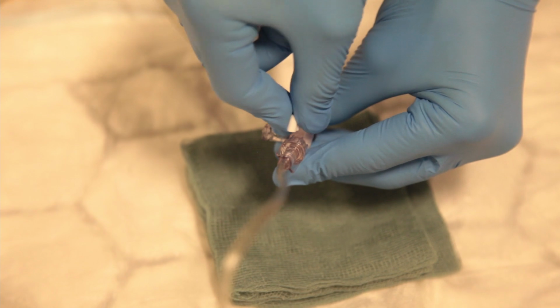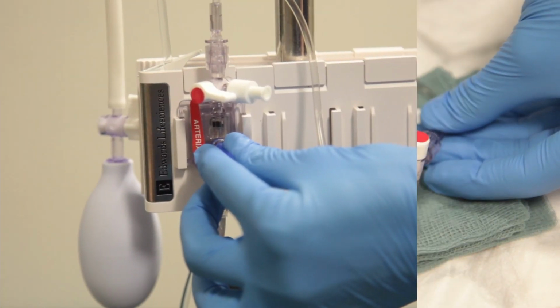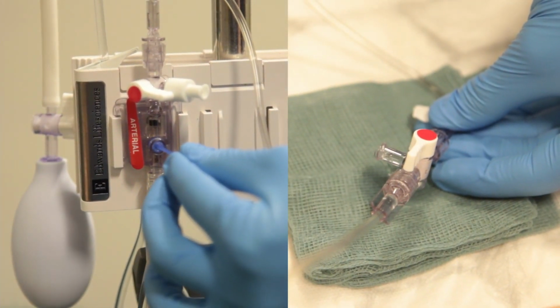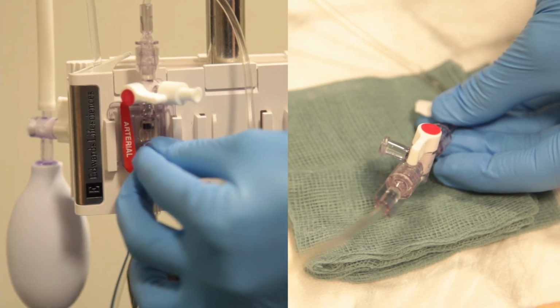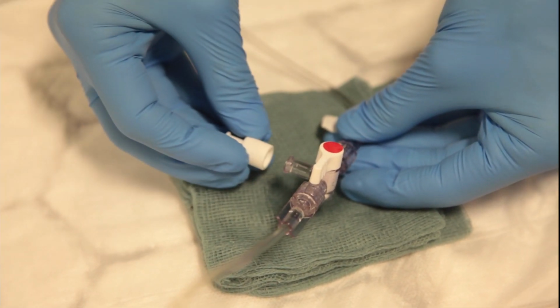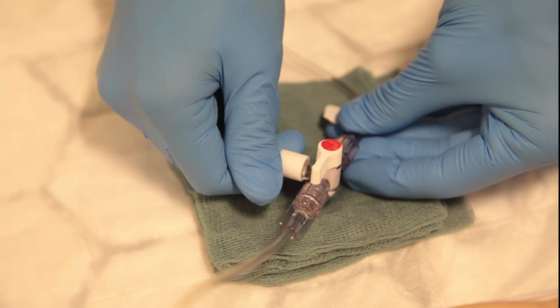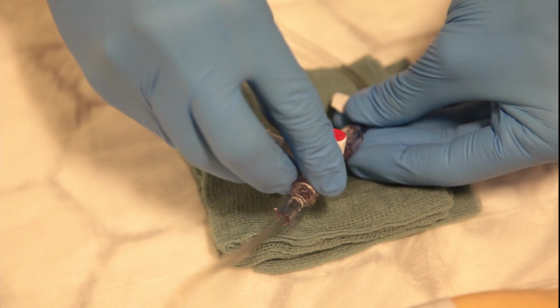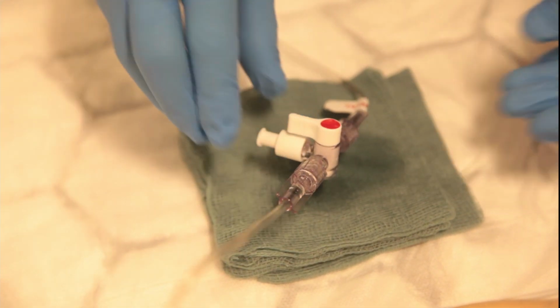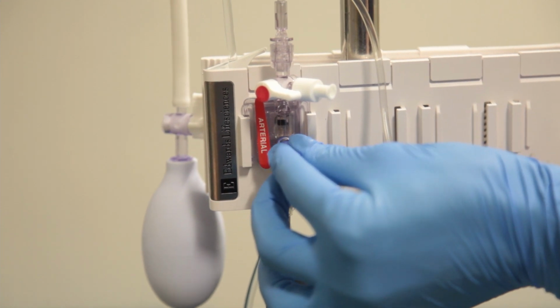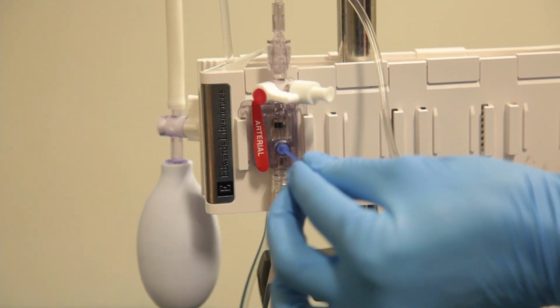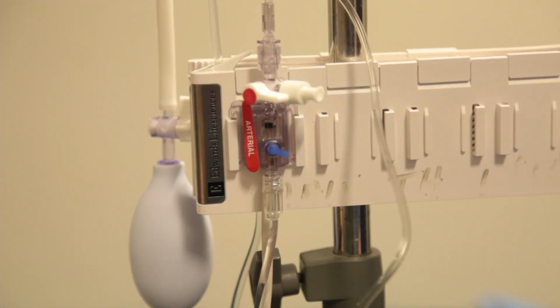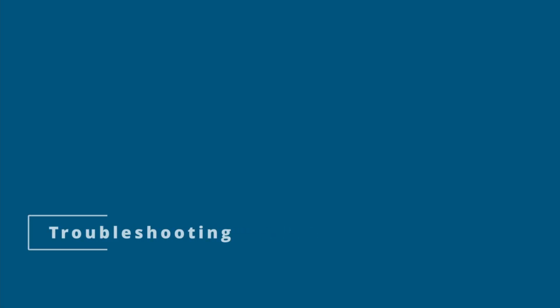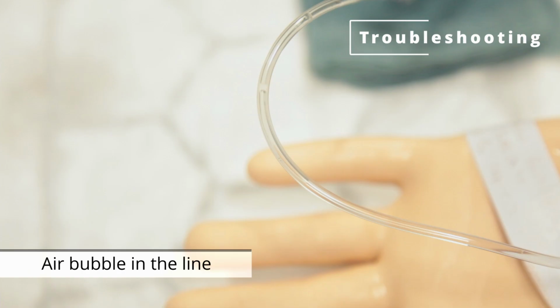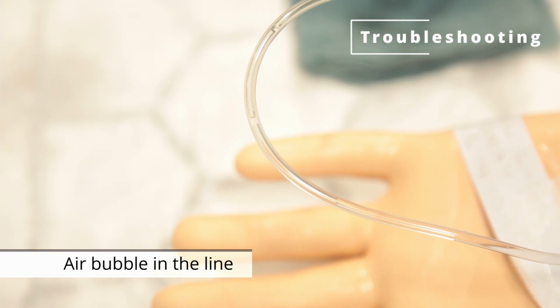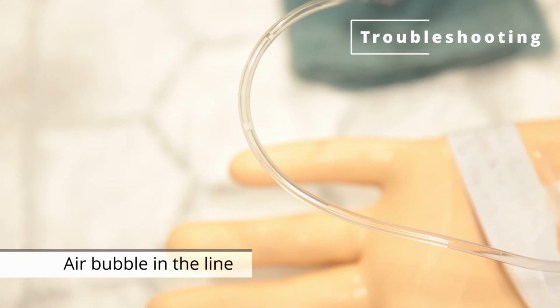Rotate the arm to be off to the patient and pull the rubber flush band to expel blood and air from the sampling port. Then rotate to neutral and replace the bung. Pull the rubber flush band and flush the line through with saline until there is no blood visible in the line itself.